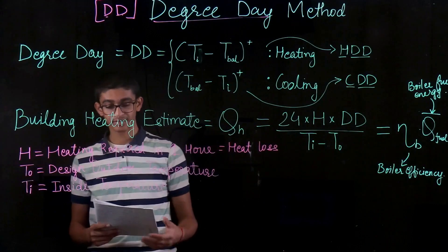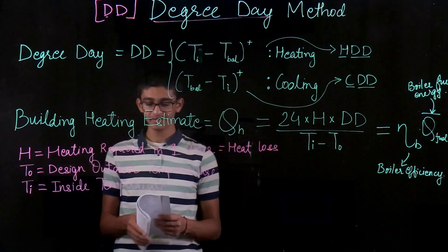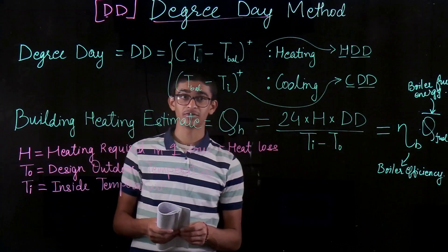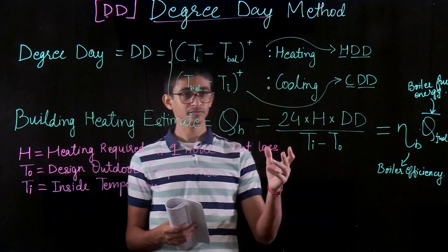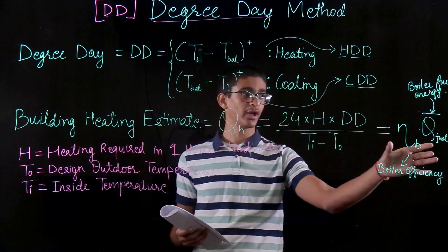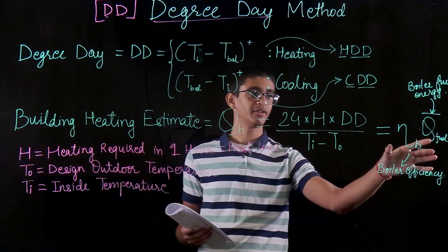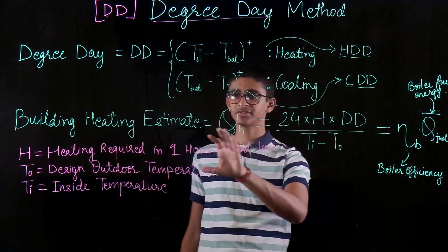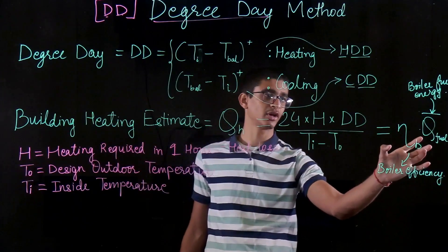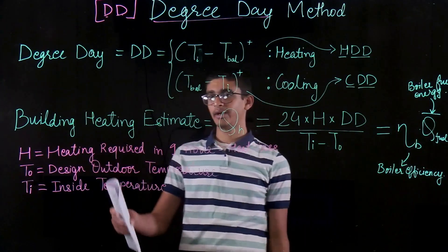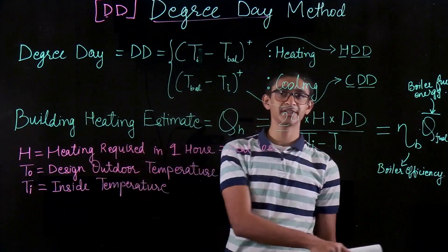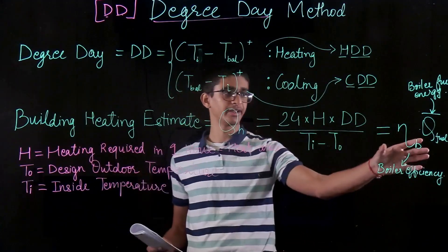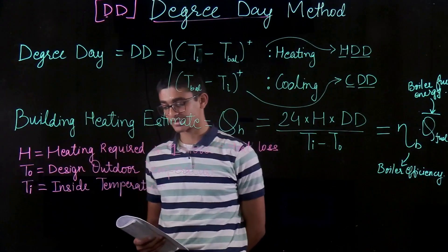The disadvantage is that there is no part-load consideration. The boiler always operates at the given efficiency, but if loads reduce, the boiler efficiency does not change in this model — which is not true in reality. Depending on the load, boiler efficiency actually changes. This formula does not take into account changes under part-load conditions.